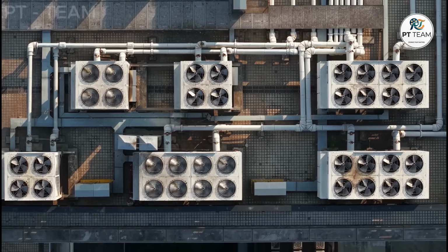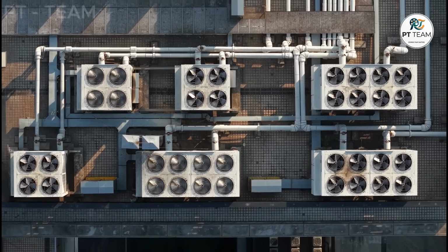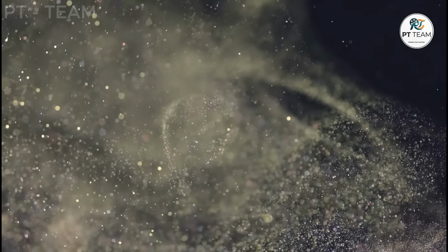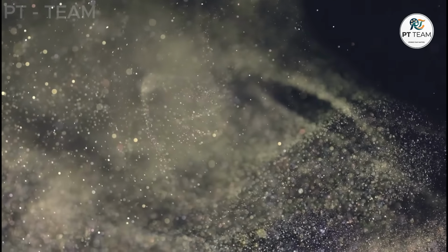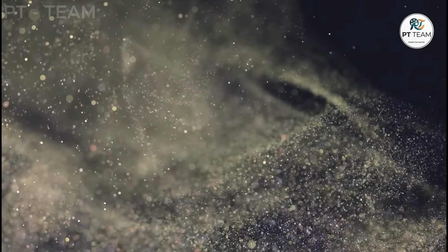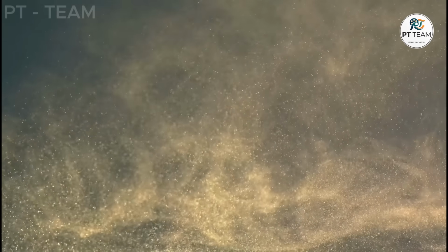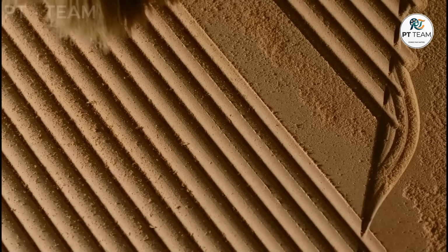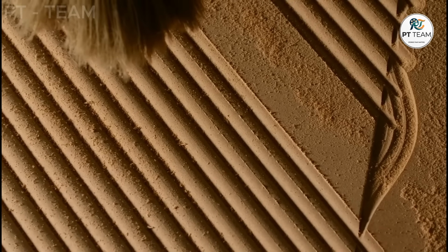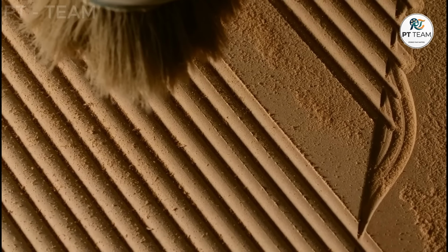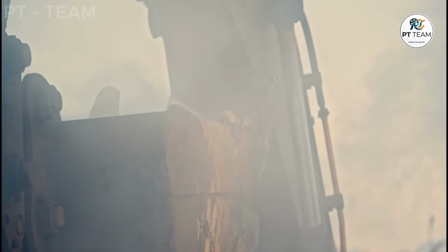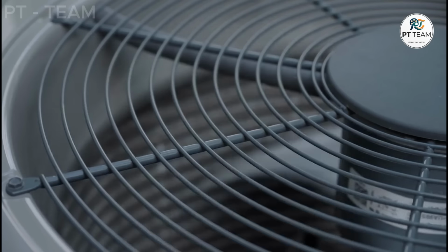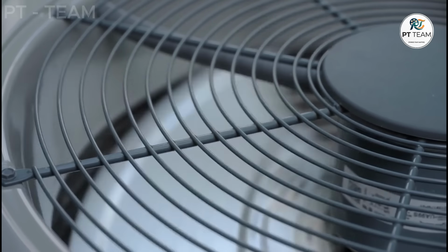The filter does not become a severe problem because it fails to catch the dust. It becomes a hidden operational burden precisely because it catches so much of it. As the days and weeks pass, the accumulation of dust begins to alter the physical properties of the filter. The initial layer of captured particles creates a foundation for the next layer to attach to. This process is known as dust loading, and it fundamentally changes how the entire air handling unit operates.